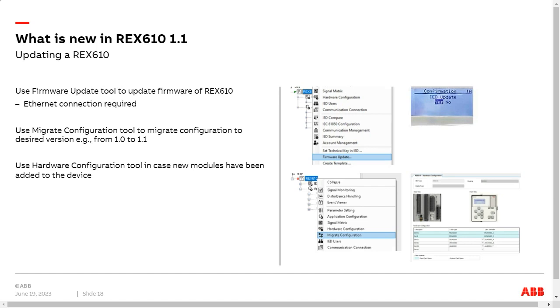After the firmware update, the new functions are available in the REX610, but you also need to tell PCM600 that this device is now a 1.1. So you right click on the REX610 and select migrate configuration, and then you select, in this case, that I want to migrate it to the 1.1. I think it's the only option as of today. Then it will update the settings in PCM600, so it will allow you to, for example, instantiate this new protection function released in the 1.1 firmware.